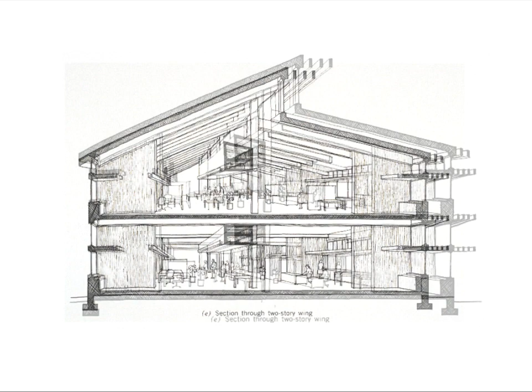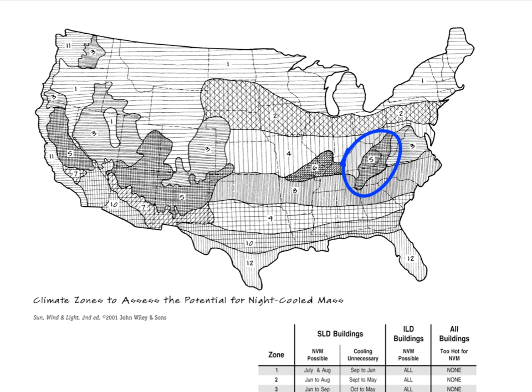In the night cooled mass strategy, you can find this map. It helps to find the zones where the potential for night cooled mass is good. So for example, Knoxville, Tennessee is in zone 5. In zone 5, in a skin load dominated building, night ventilation is possible typically from about May to September. And then from October to April, typically we would not use cooling at all. In an internal loaded building, it might be possible in all months in zone 5. And it would be too hot for night ventilation hardly ever, right?